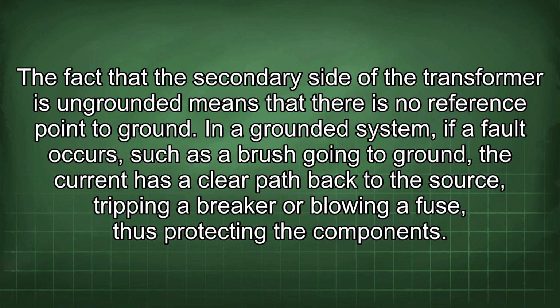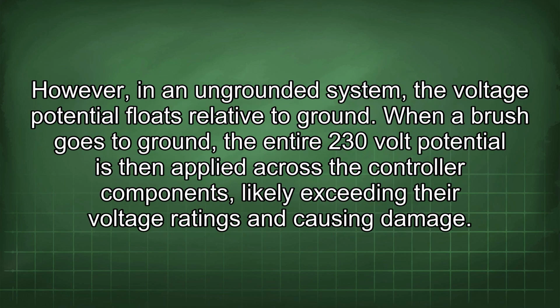The fact that the secondary side of the transformer is ungrounded means that there is no reference point to ground. In a grounded system, if a fault occurs, such as a brush going to ground, the current has a clear path back to the source, tripping a breaker or blowing a fuse, thus protecting the components. However, in an ungrounded system, the voltage potential floats relative to ground. When a brush goes to ground, the entire 230-volt potential is then applied across the controller components, likely exceeding their voltage ratings and causing damage.